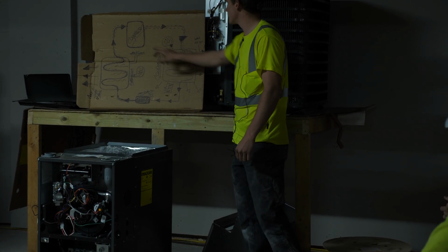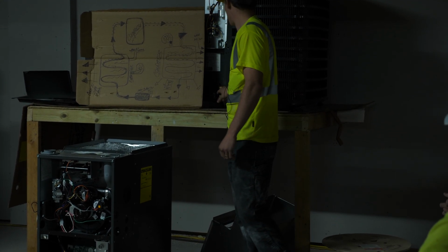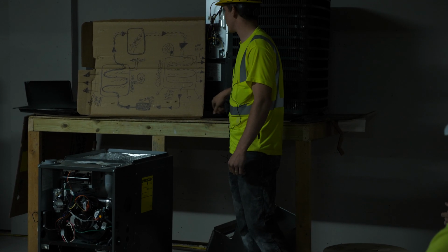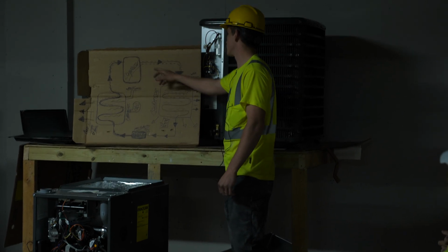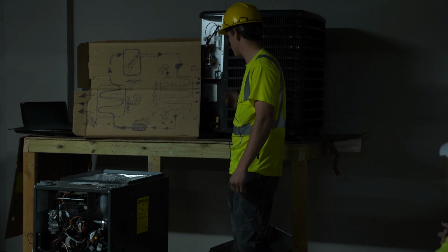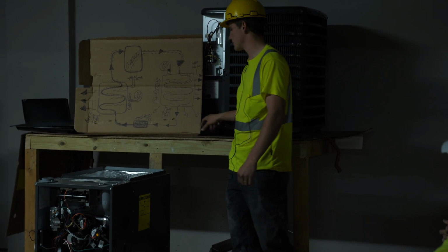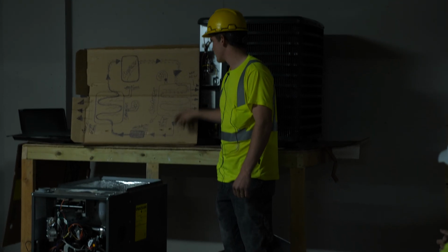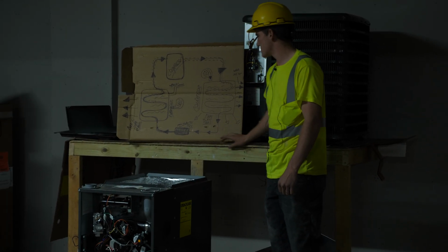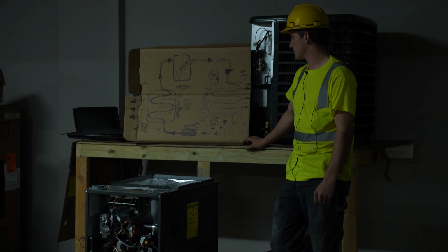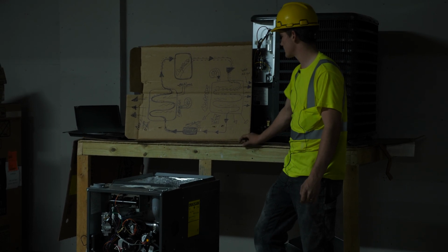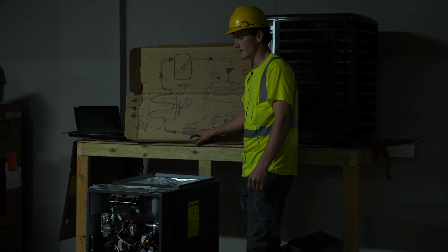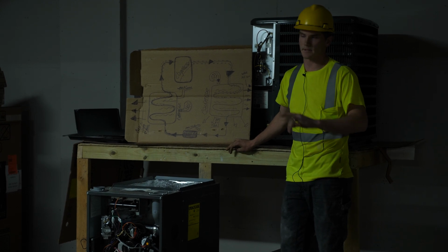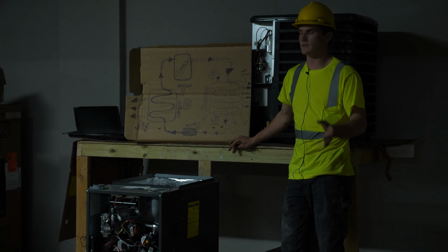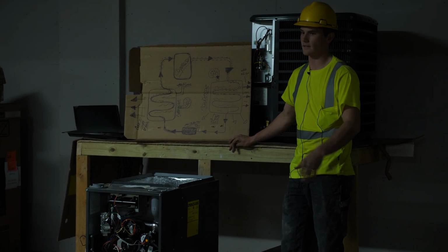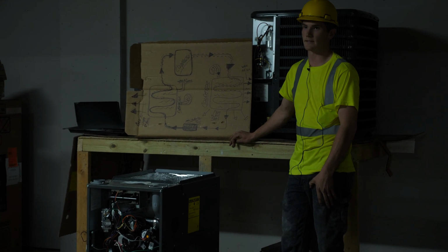So from the A-coil, there's a gas line going in, and then into the compressor, gas, and then it changes from a gas to a liquid, out the liquid line, and then it goes through the TXV metering device. This is the TXV. So the TXV just keeps the high pressure and the low pressure away from each other, to make sure that the system doesn't blow up, essentially.